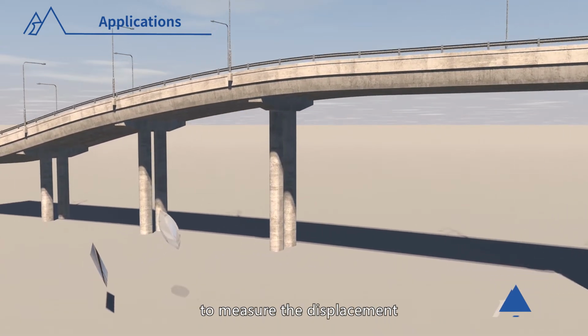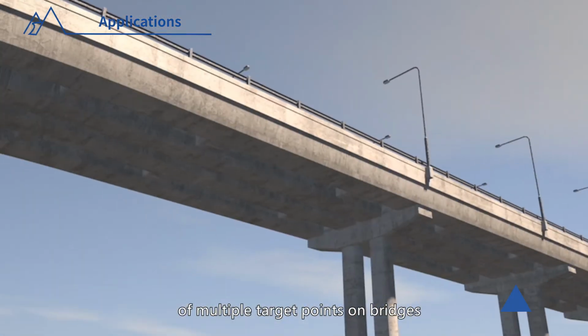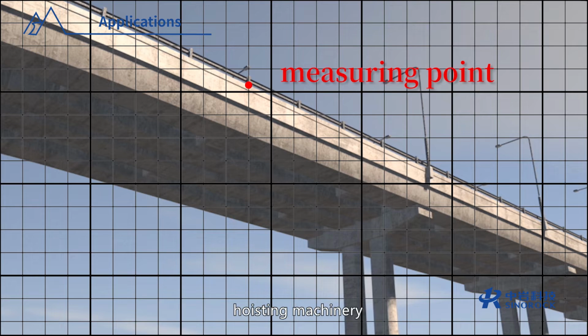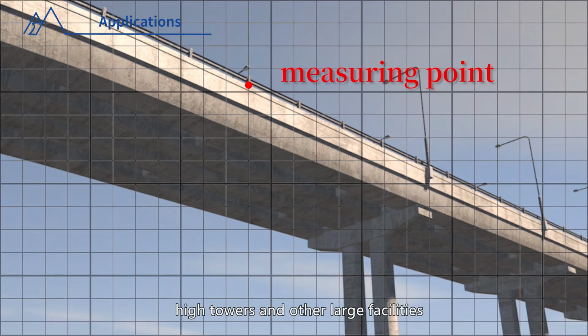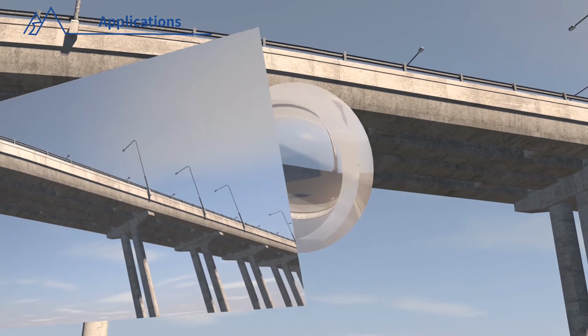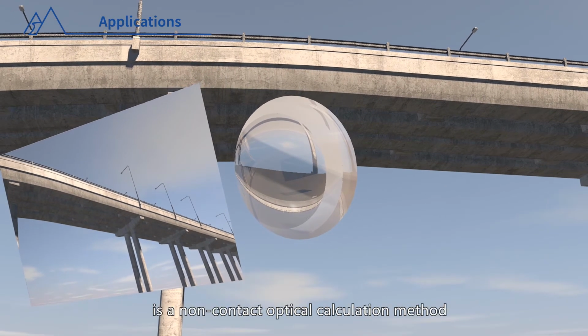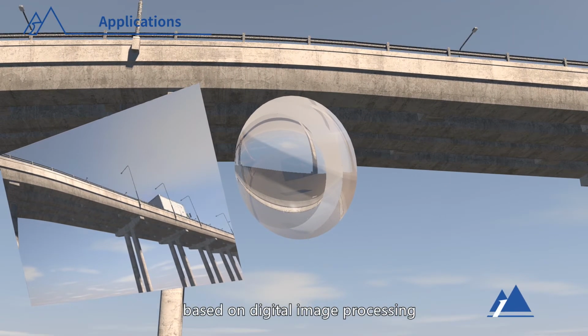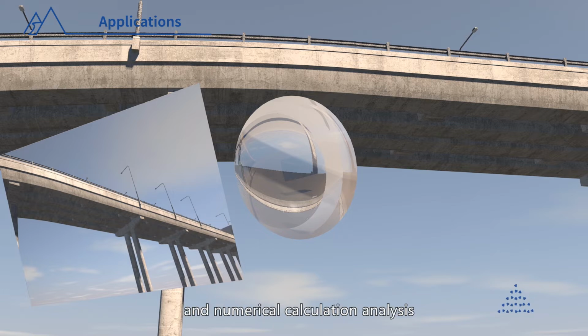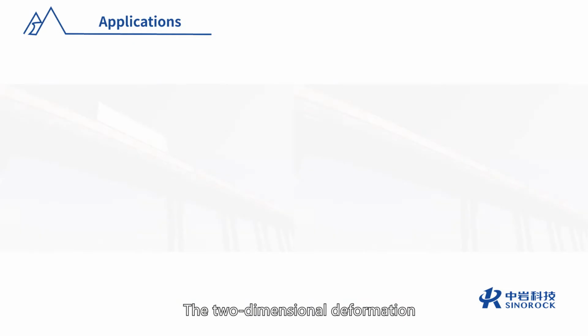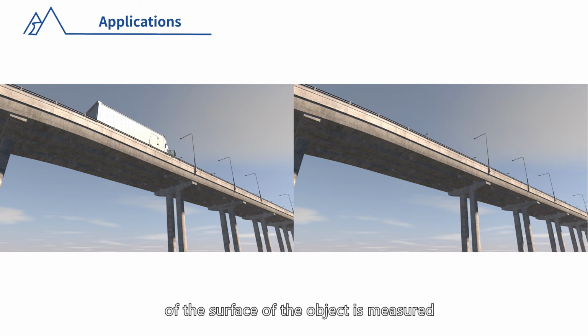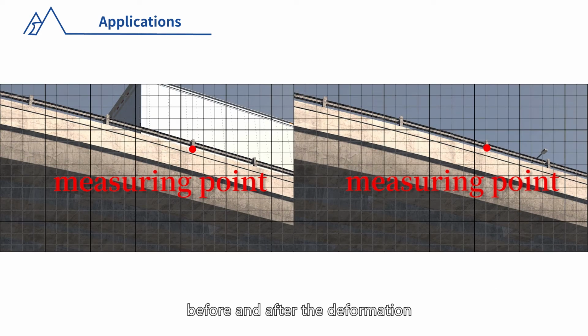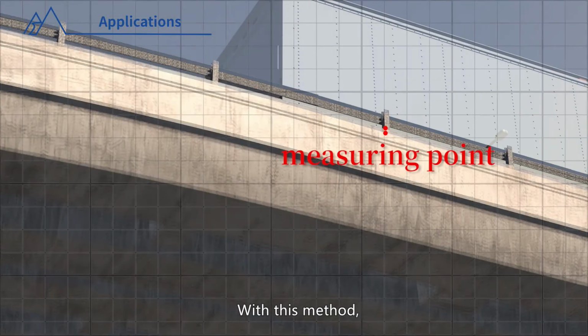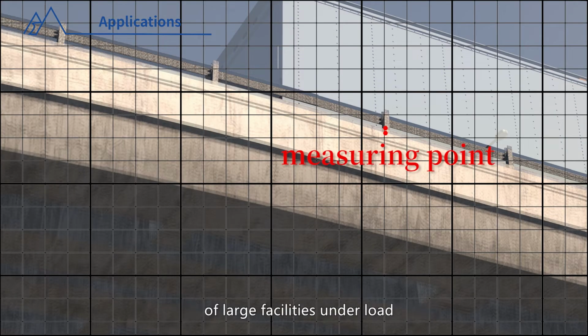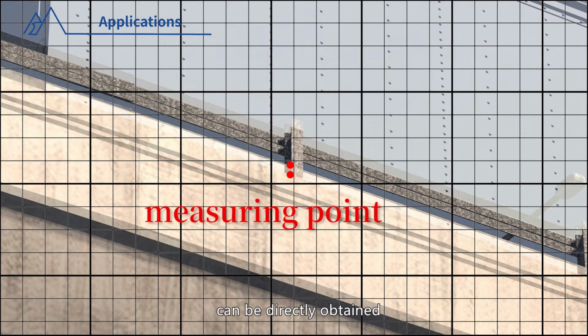The principle of this instrument is based on the pinhole imaging model, using the digital image correlation algorithm, DIC, to measure the displacement of multiple target points on bridges, tunnels, hoisting machinery, high towers, and other large facilities in real time. Digital image correlation is a non-contact optical calculation method based on digital image processing and numerical calculation analysis. The two-dimensional deformation of the surface of the object is measured by the two images before and after the deformation. With this method, the displacement and deformation fields of large facilities under load can be directly obtained without installing any sensors or marking points.